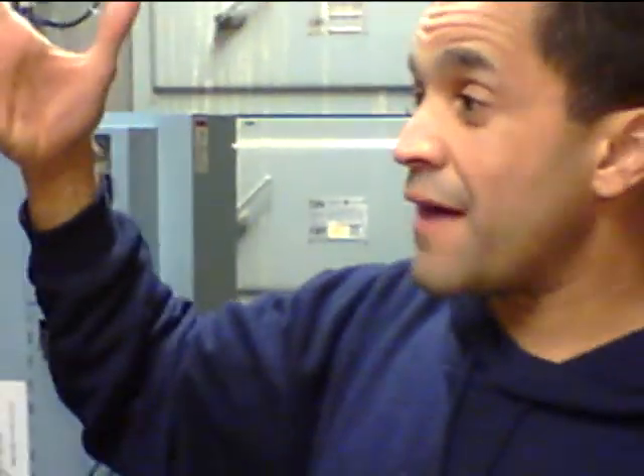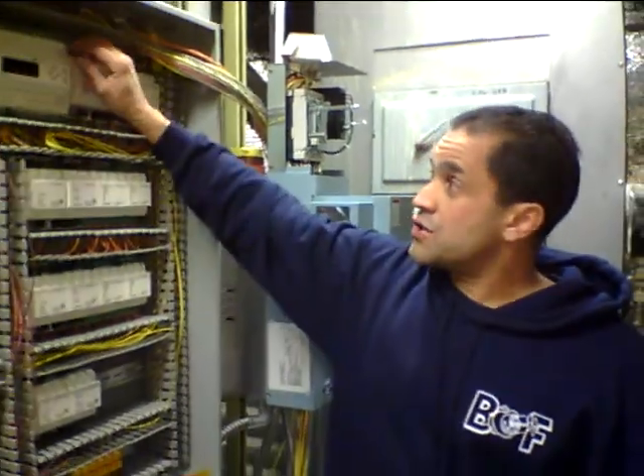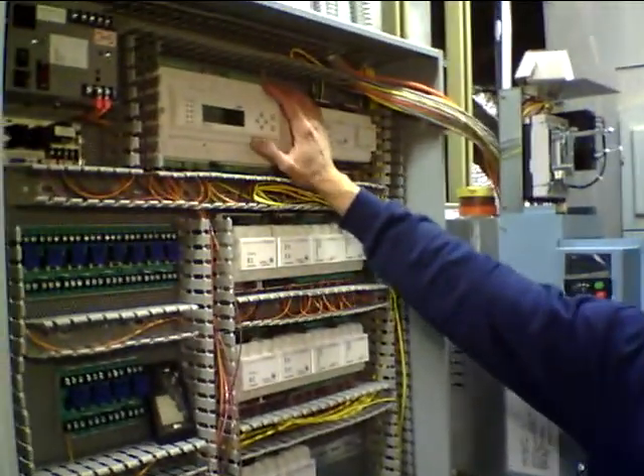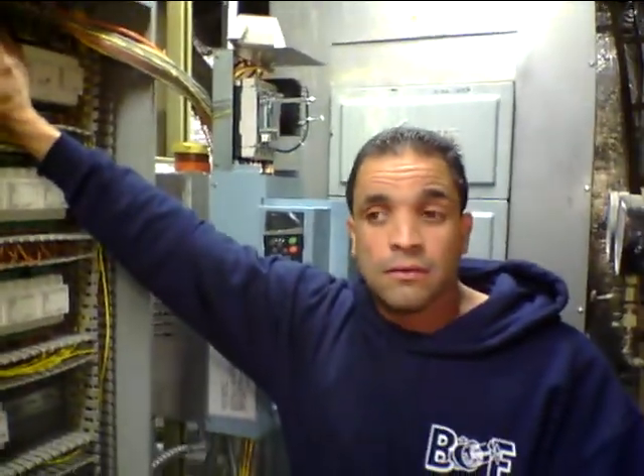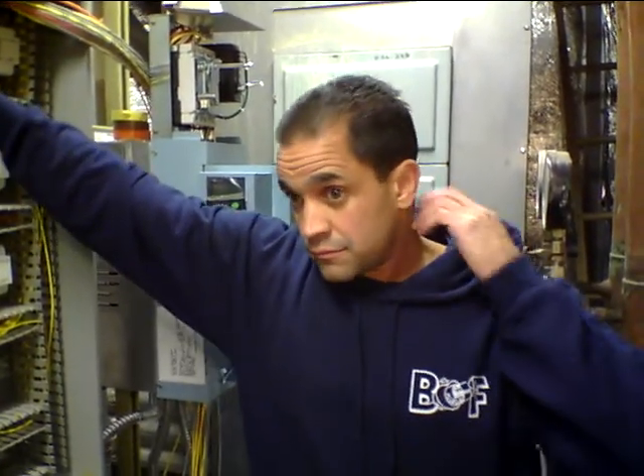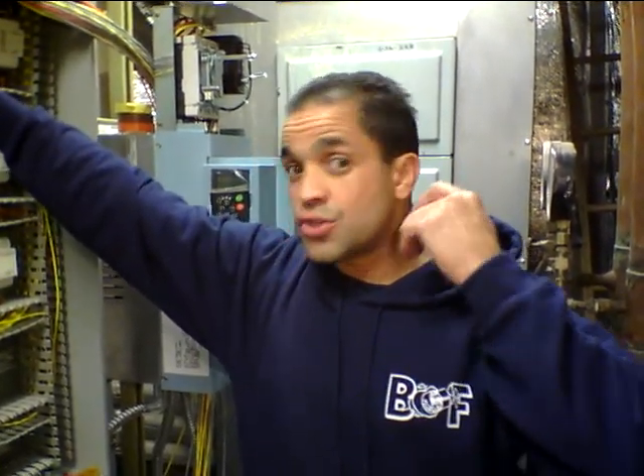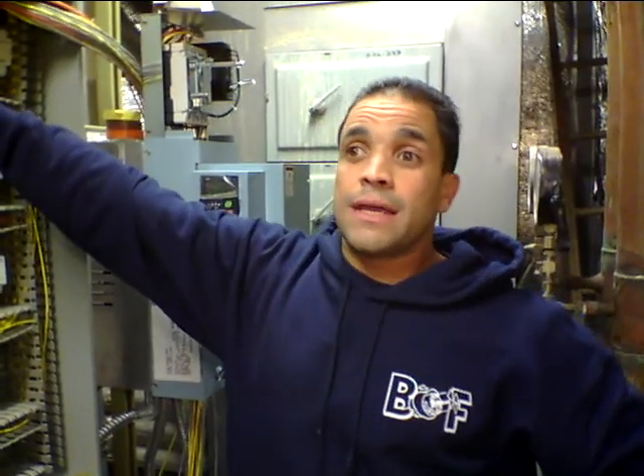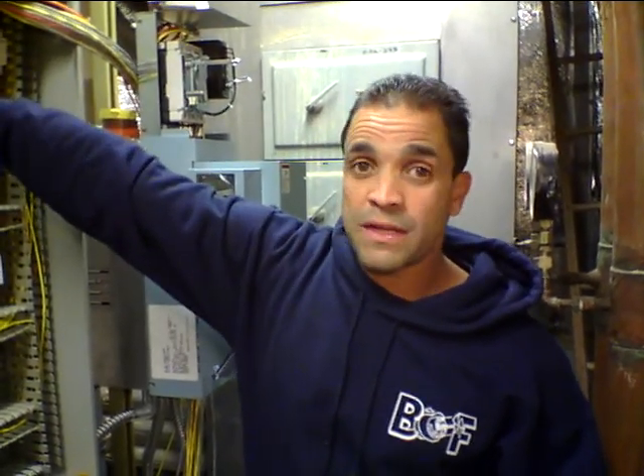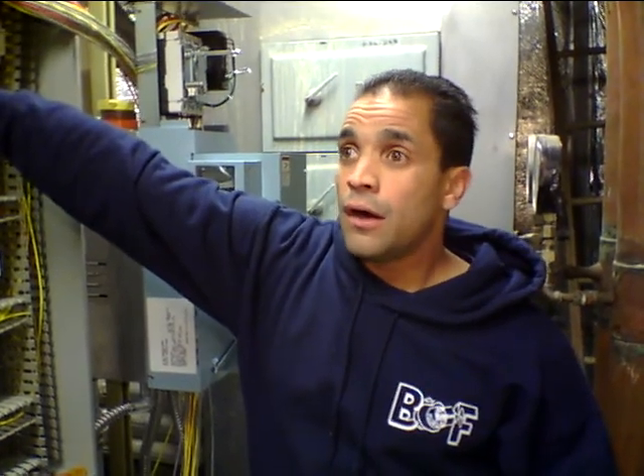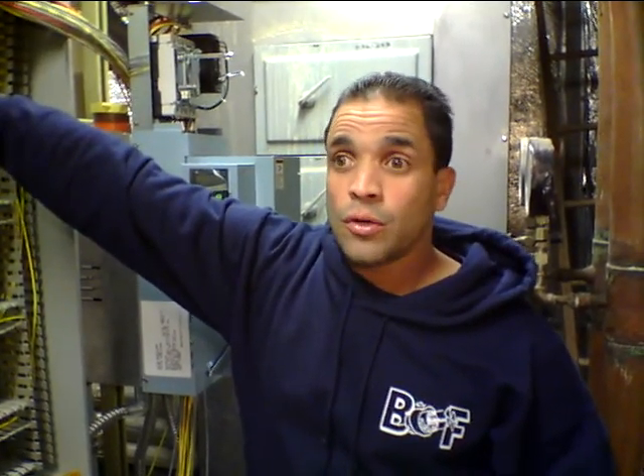Like I said before, 5 circuits. On this controller, we're going to be able to monitor superheats, high pressure, low pressure, condenser water in, condenser water out. We can also do free cooling with this, because we have the capability of taking the towers and speeding up those fans, and on a cool day, we could actually get 55-degree water — good enough to cool this building down.